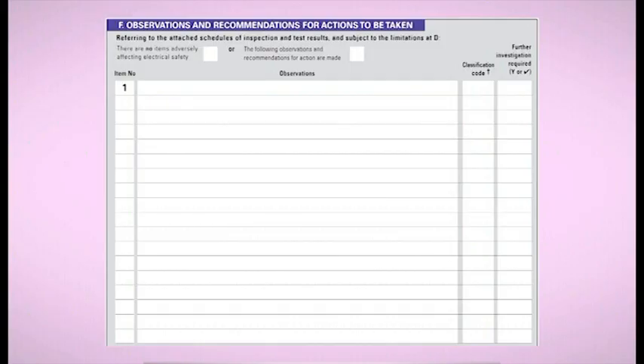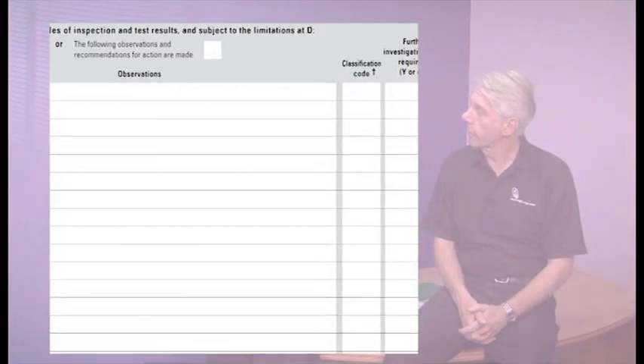However, operational limitations are issues that have arisen whilst carrying out the report, which have prevented either inspection or testing of a particular item. Again, the reason must also be recorded. An example might be that access may be restricted to lighting, perhaps because of height or because a loft is inaccessible. Another change with the EICR is the codes used to classify observations.